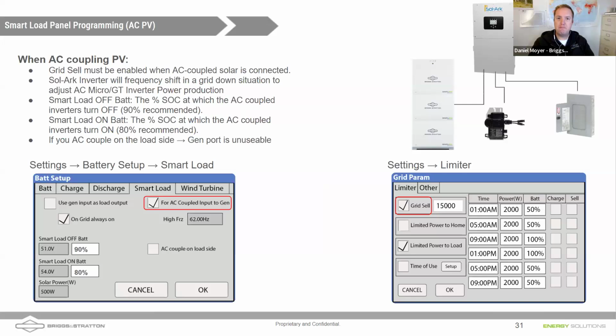Okay, for settings here, in that same smart load tab, again, the smart load just refers to the generator port. We'll check the box for AC coupled solar input to the generator. High frequency here, it's going to shut those microinverters off by going above 62 hertz. That's the standard here in North America. So that's the 1741 SB. And then on grid, always on. So as long as the grid is up, you can have that box checked, and then those microinverters can always just send excess power back to the utility there.